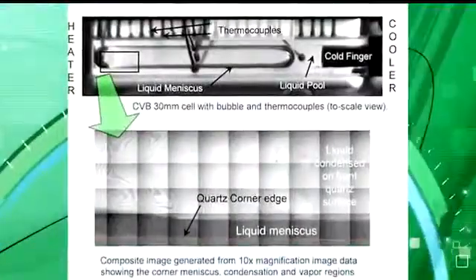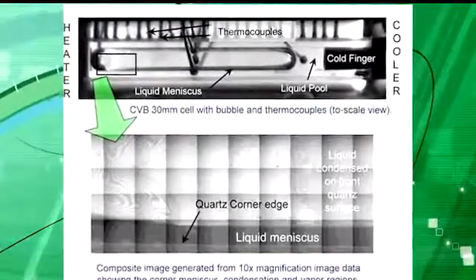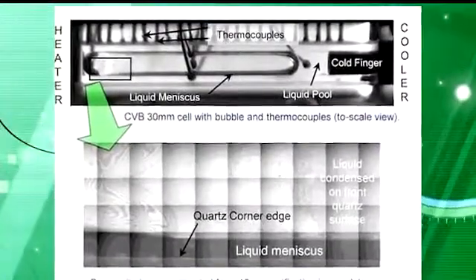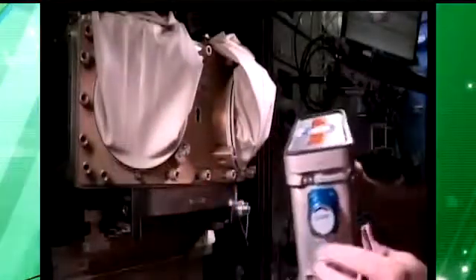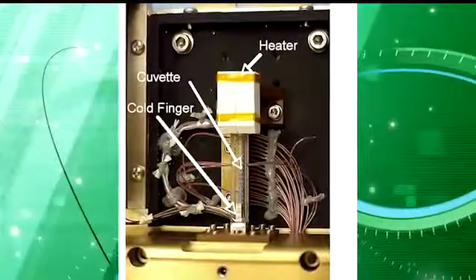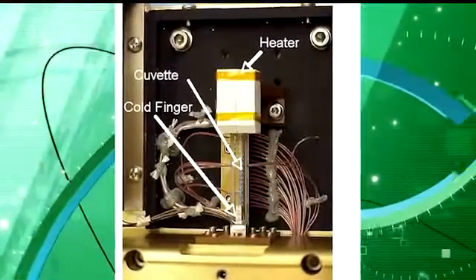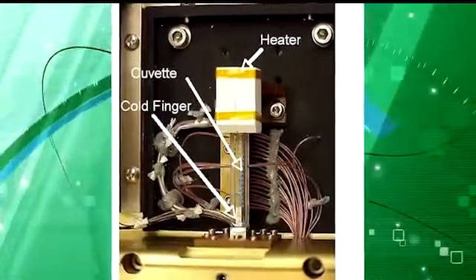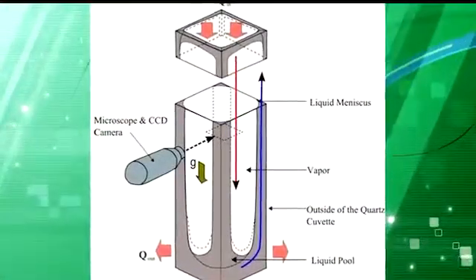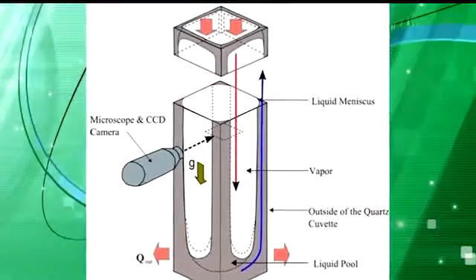And now that fluid can flow towards a heat source in order to cool the heat source. So you get evaporation where you get the cooling. Now, in our device, it's closed and it's underfilled, so you have a vapor bubble in there. So the liquid is in the corner, the vapor bubble is in the central part. So at the hot end, you get evaporation, vapor flows down the center, the vapor bubble, to the cold end where it condenses and then is sucked back.